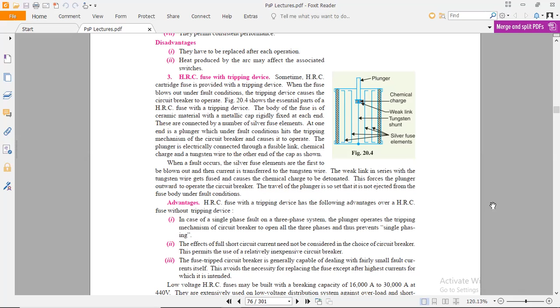The low voltage HRC fuses, which are used on the LV side, may be built with a breaking capacity of 16,000 amperes. This is the breaking capacity of fuses that can be handled here. Breaking capacity is the enormous amount of current the device can handle at the moment of fault, and it is 16 kiloamperes to 30 kiloamperes at 440 volts.